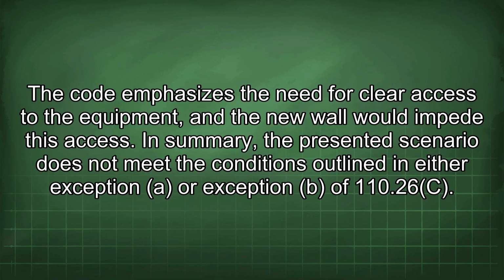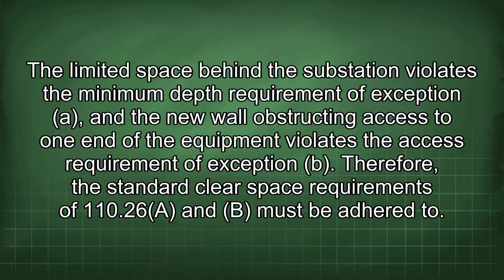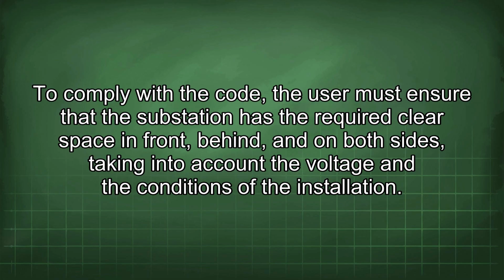In summary, the presented scenario does not meet the conditions outlined in either Exception A or Exception B of 110.26(C). The limited space behind the substation violates the minimum depth requirement of Exception A, and the new wall obstructing access to one end of the equipment violates the access requirement of Exception B. Therefore, the standard clear space requirements of 110.26(A) and (B) must be adhered to. To comply with the code, the user must ensure that the substation has the required clear space in front, behind, and on both sides, taking into account the voltage and the conditions of the installation.